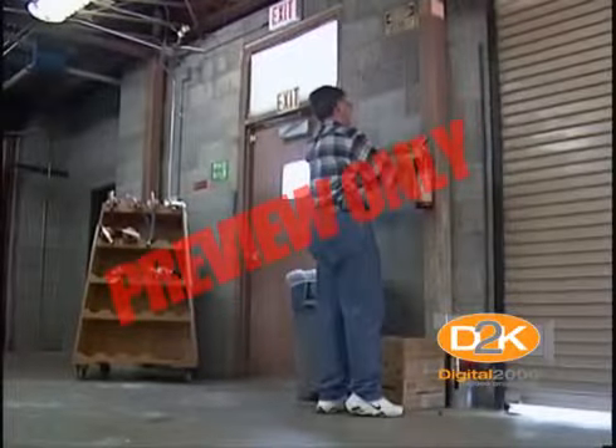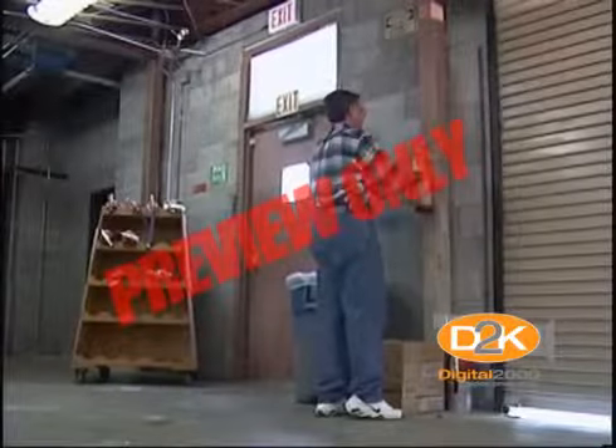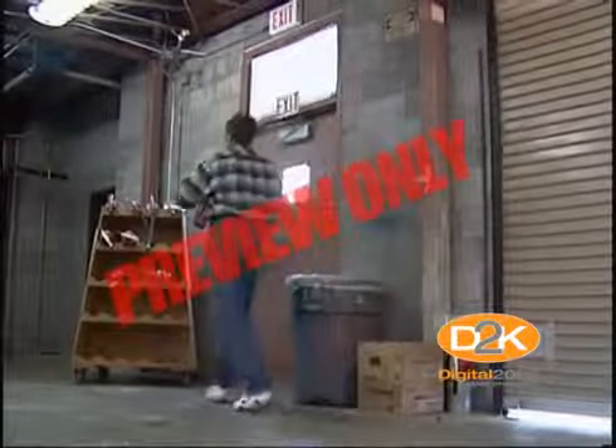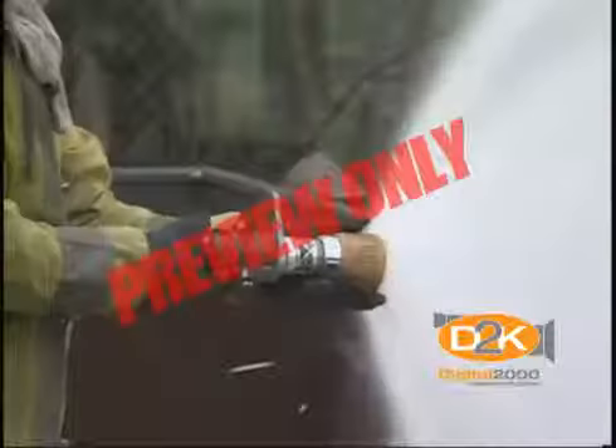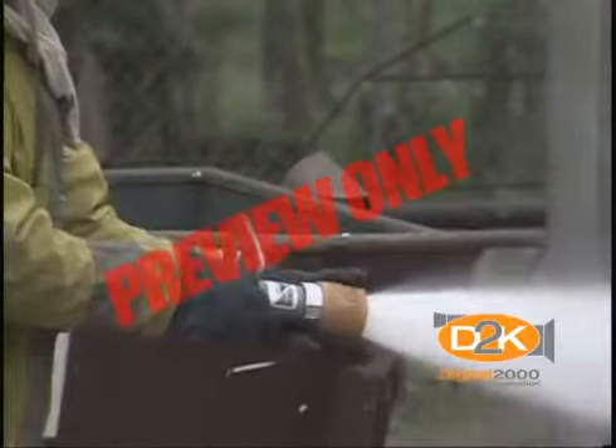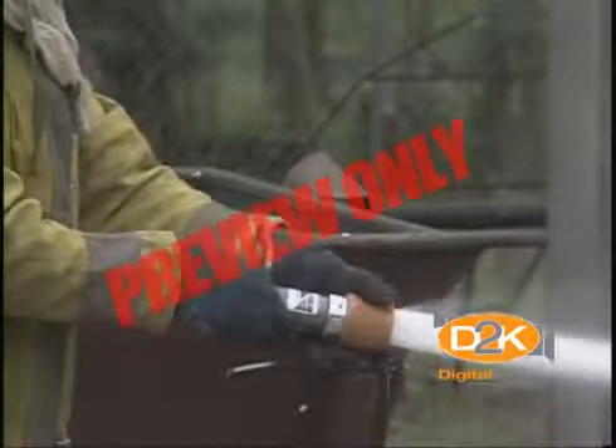7. Use only a water-filled fire extinguisher on a pool chlorinating chemical fire. Never use a dry chemical fire extinguisher on a pool chlorinating chemical fire. It may cause an explosion. Summon help immediately, because the best way to fight a fire involving pool chemicals is to flood with extremely large amounts of water, such as is available through the fire department.